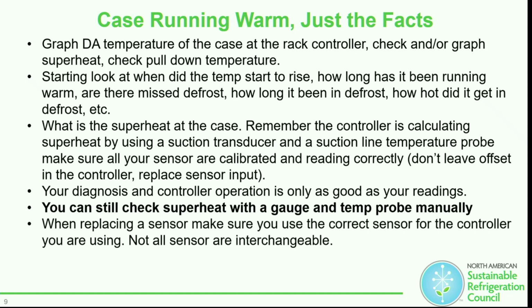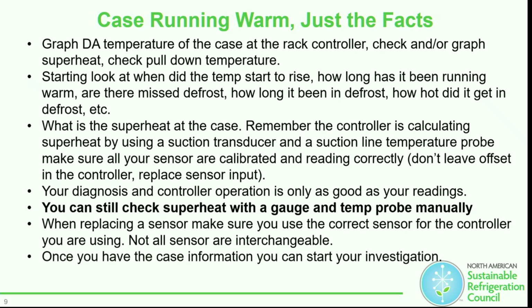When replacing a temperature sensor, make sure you use the correct temperature sensor for the controller that you're using. Not all temperature sensors are interchangeable. I will say BAPI is a manufacturer that makes sensors for everybody. There is something called a 10K2, and there's also a 10K3. So not all 10Ks are equal, right? They have different curves, and it might interfere with your defrost operation as well as your actual case temperature. Once you have the case information, you can start your investigation.